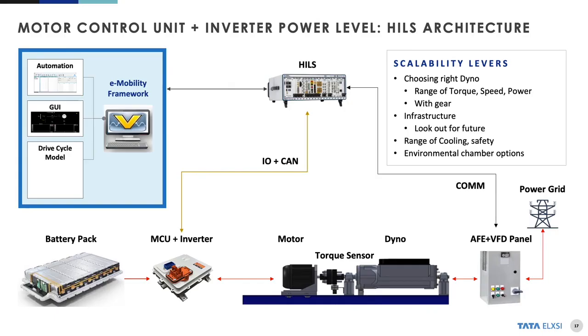Generation of energy from the dyno creates a mechanical loading effect on the motor, since both are coupled through a common shaft. This loading effect the motor now experiences is equal to the initial loading torque given as input to the VFD. Since the dyno is generating energy, it is converted to a proper format by AFE and pushed back to the grid.